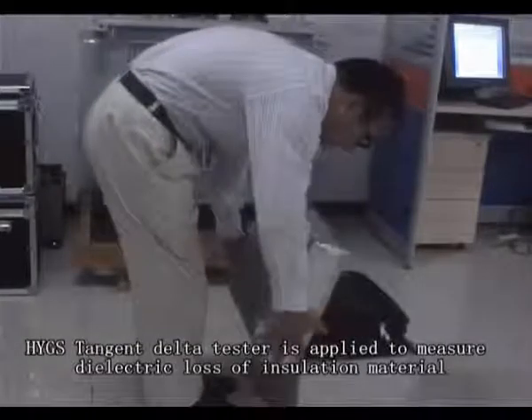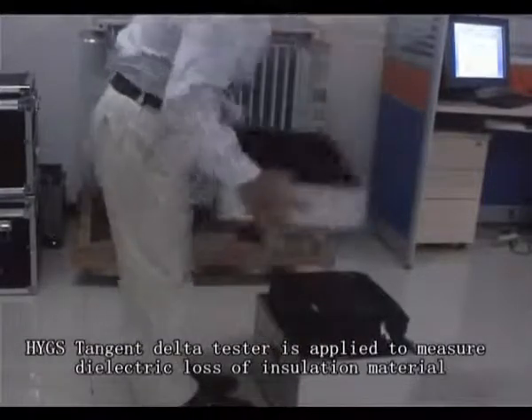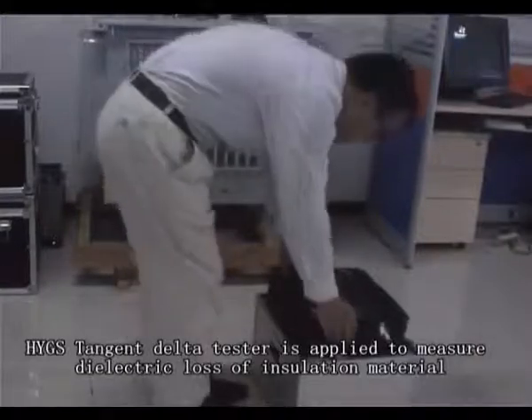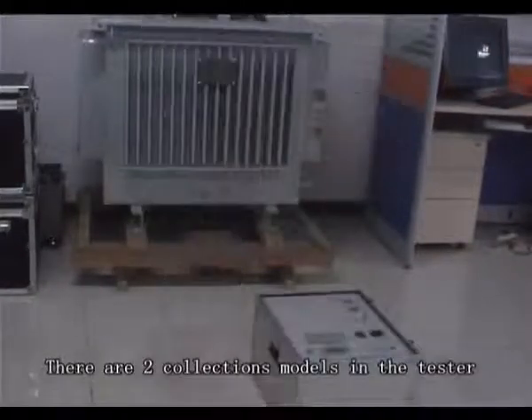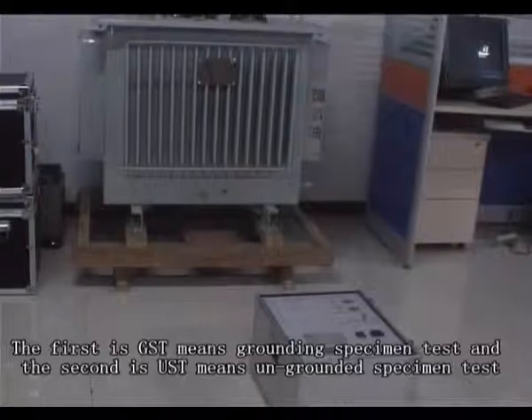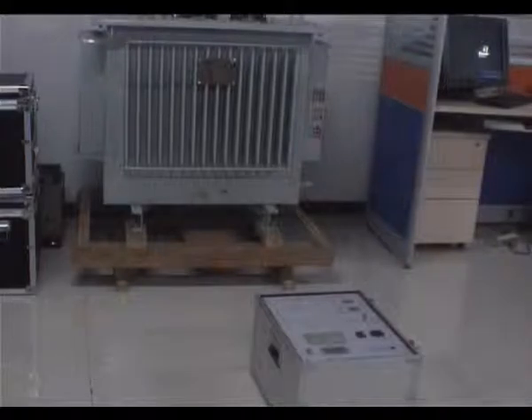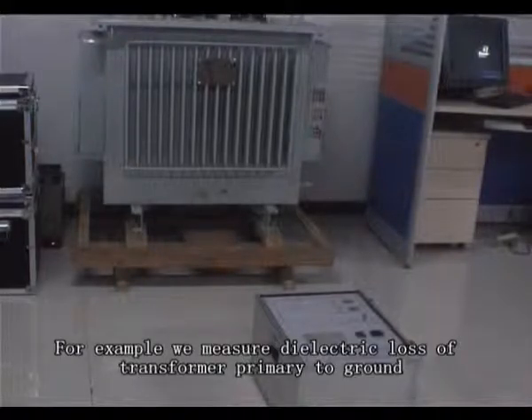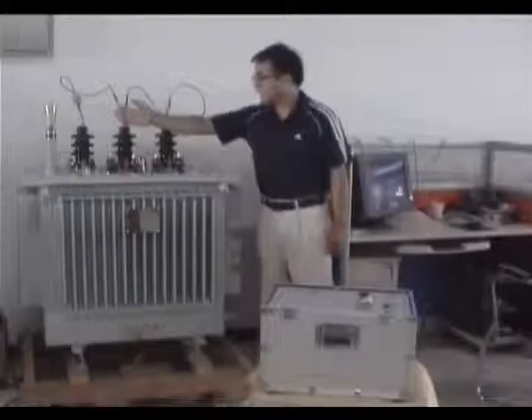The HYGS tangent delta tester is applied to measure dielectric loss of insulation material. There are two connection modes in the tester. The first is GST, meaning grounding specimen test, and the second is UST, meaning ungrounded specimen test. For example, we measure dielectric loss of the transformer primary to ground.